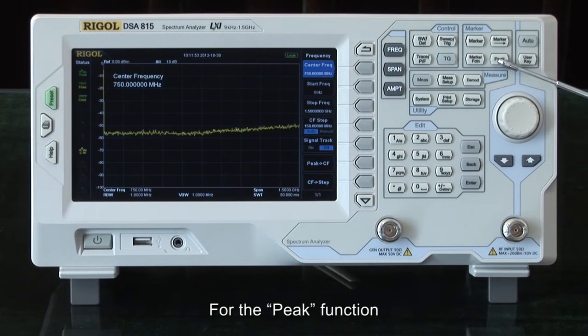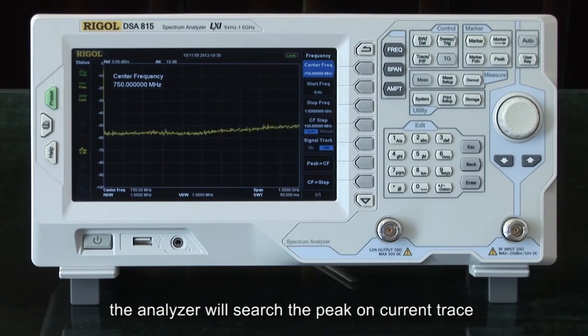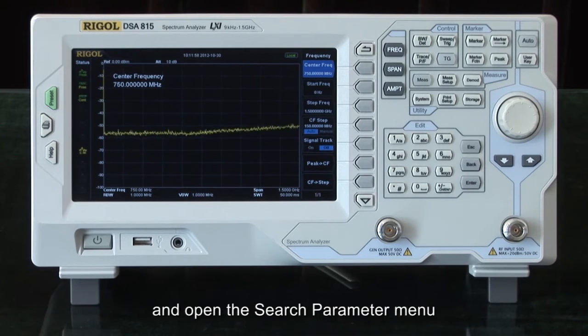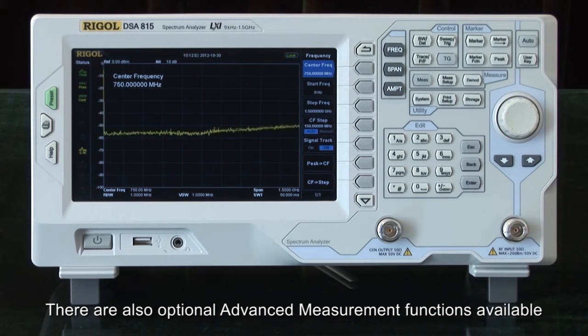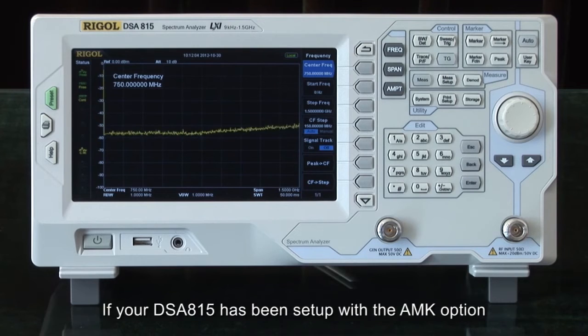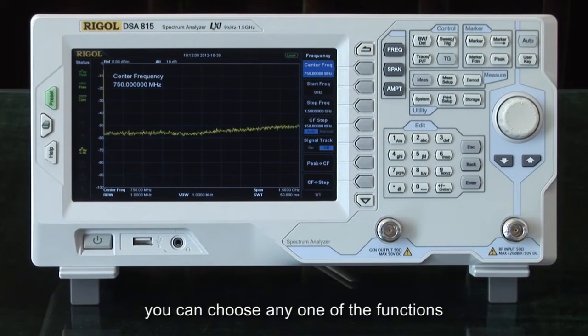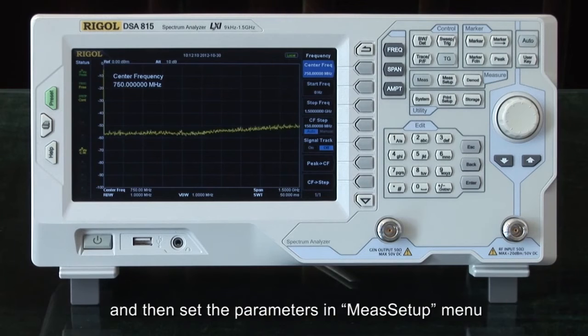For the peak function, once you press the down button, the analyzer will search the peak on the current trace and open the search parameter menu. There are also optional advanced measurement functions available. If your DSA815 has been set up with the AMK option, you can choose any of the functions and set the parameters in the Measure Setup menu.